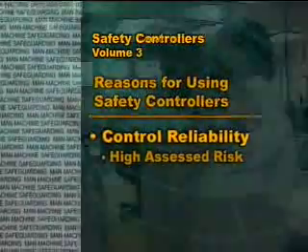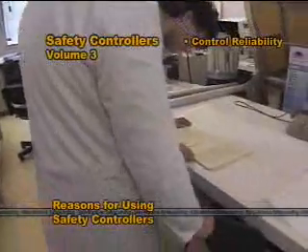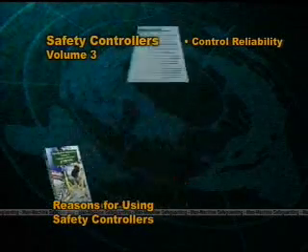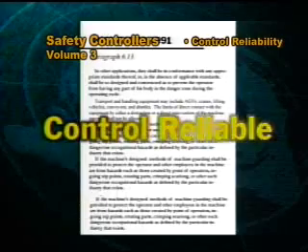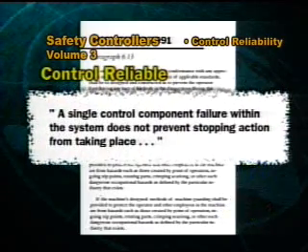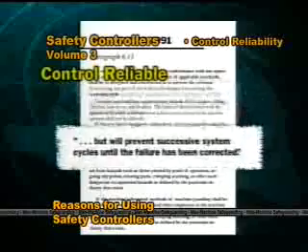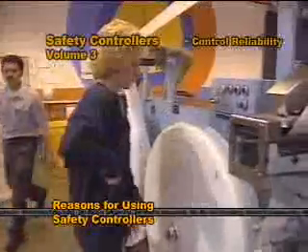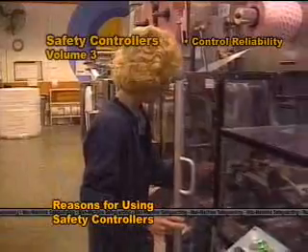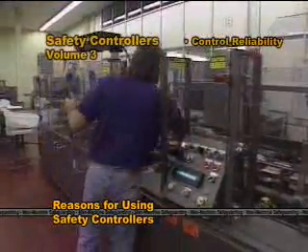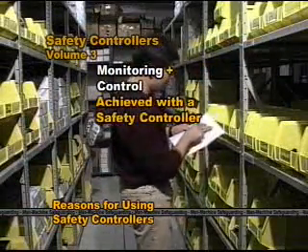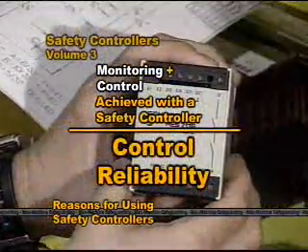Safety controllers can also be used where a system designer wishes to satisfy control reliability requirements. A safety system is control reliable only if it's designed so that any single component failure does not prevent the machine from stopping and does prevent it from restarting until the fault has been corrected. Achieving control reliability requires constant monitoring of the safety system to permit detection of a fault that might prevent machine stoppage. Once detected, the machine must be prevented from restarting until the fault has been corrected. This monitoring and control can be achieved with an appropriate safety controller, thus realizing control reliability.